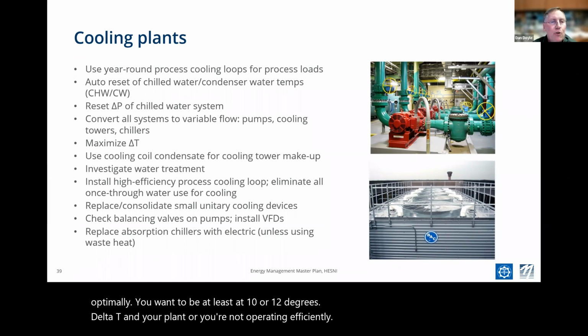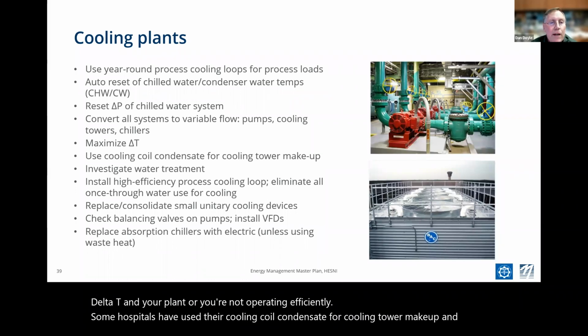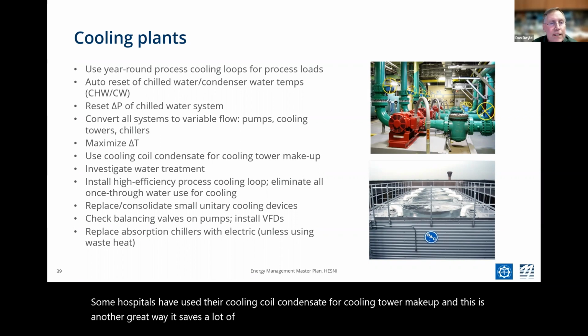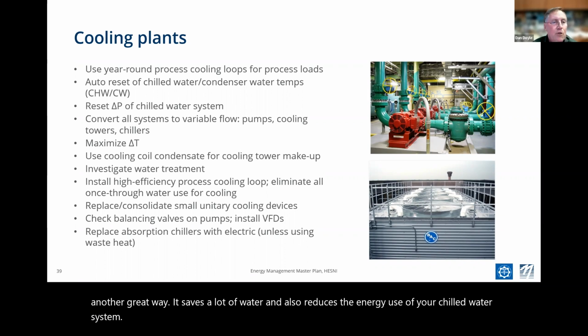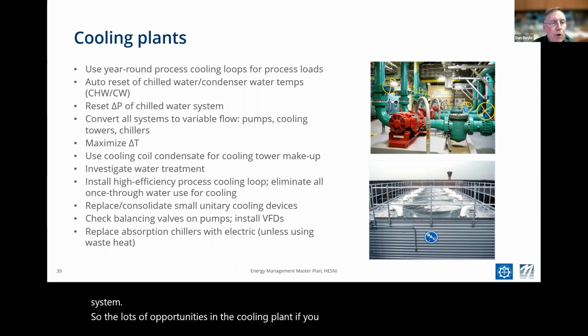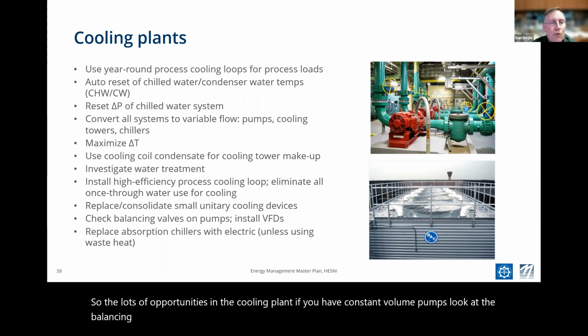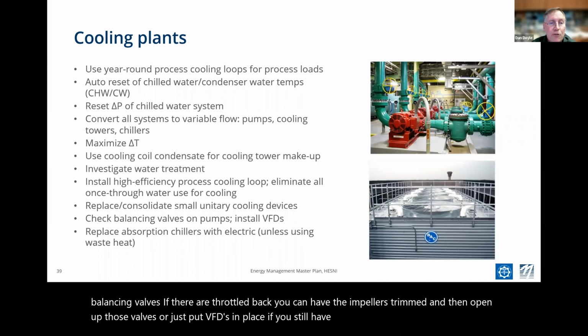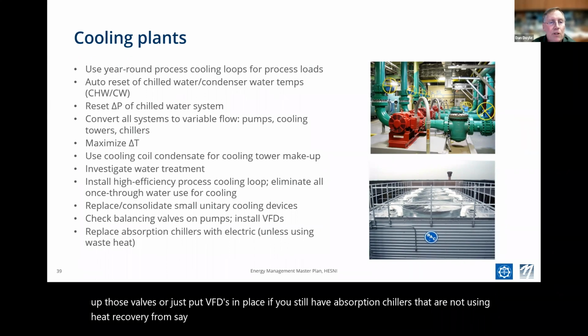Some hospitals have used their cooling coil condensate for cooling tower makeup, and this is another great way. It saves a lot of water and also reduces the energy use of your chilled water system. So there are lots of opportunities in the cooling plant. If you have constant volume pumps, look at the balancing valves. If they're throttled back, you can have the impellers trimmed and then open up those valves, or just put VFDs in place. If you still have absorption chillers that are not using heat recovery from, say, a CHP plant, then you want to look at converting those, replacing those with electric chillers.